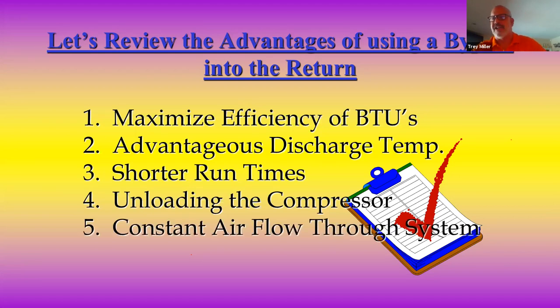Guys, I'm going to keep constant airflow through the system. Like I said, with the SBD, we're going to capture design static. This is huge. It hasn't been done before. This changes the ball game. If I can keep constant airflow through the system at all times, the unit doesn't know it has zoning on it. By maintaining the design static that the system was designed with, that particular system, that particular duct system, that's the beauty of this.